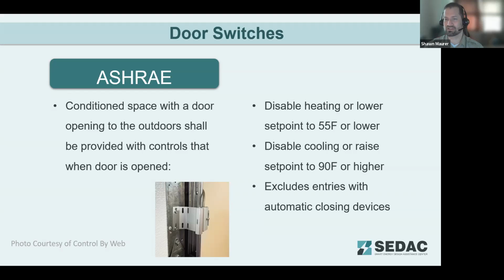Again, this is the criteria that applies if you're designing into a building a space that's alternately an open patio in mild weather and an enclosed portion of the building during more inclement weather. You're providing neutral conditioning from the air conditioning system if it's active, or just completely disabling it to minimize energy consumption and prevent waste of conditioned air going out those open patio entries.